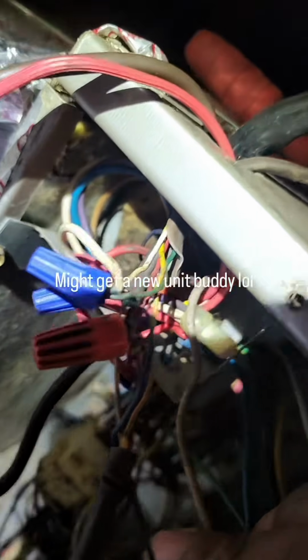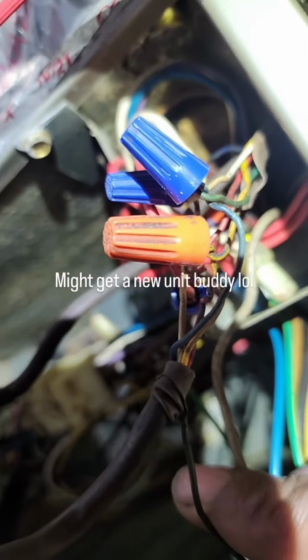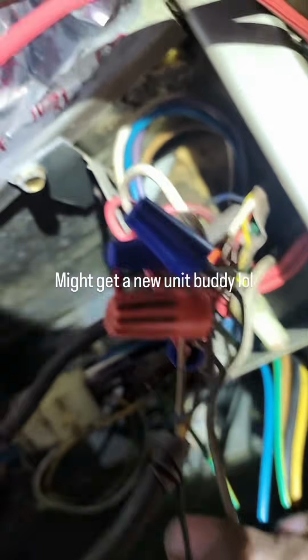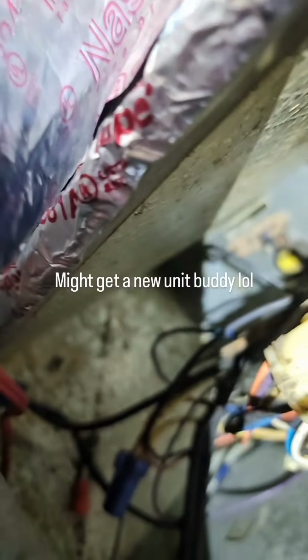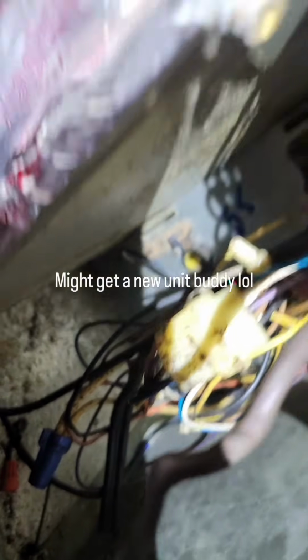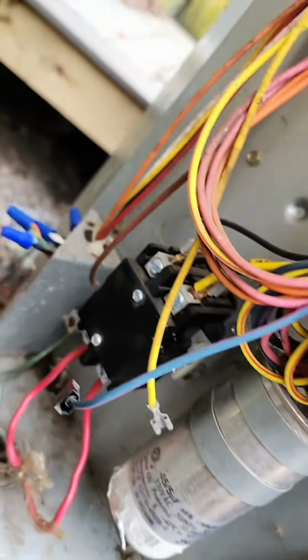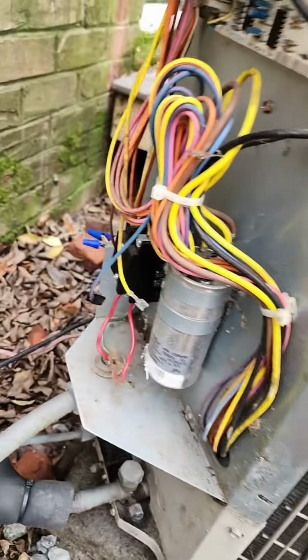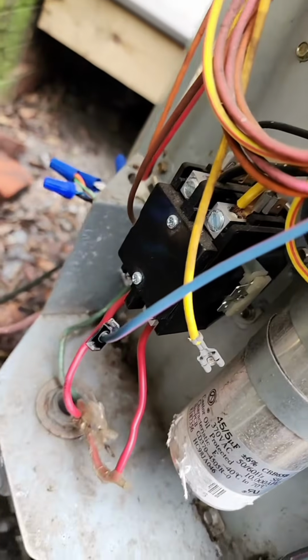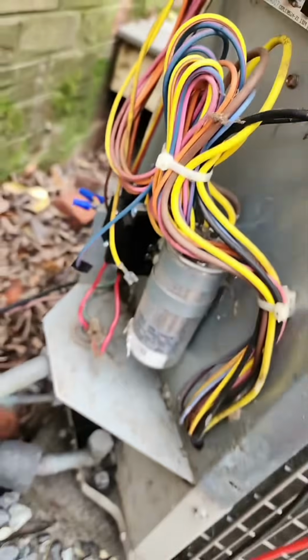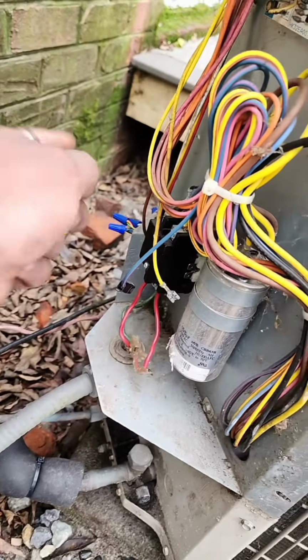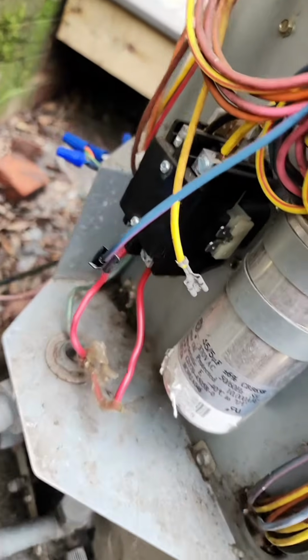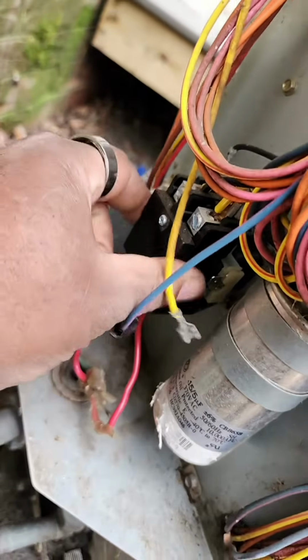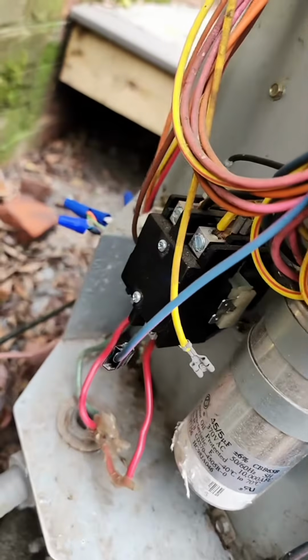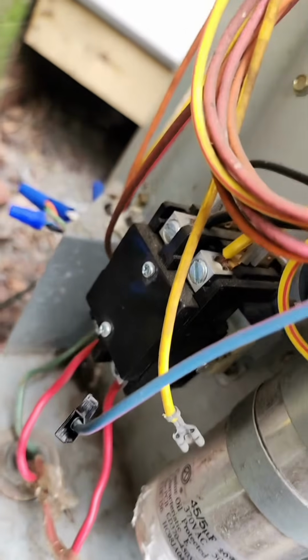So why the F did this thing blow up? Contactor shorted. It's crazy. No, it's not. It's not crazy at all. Alright, so they changed the thermostat, blew up the transformer, simultaneously blew up the contactor outside. So putting in another contactor, shit shouldn't blow up again.